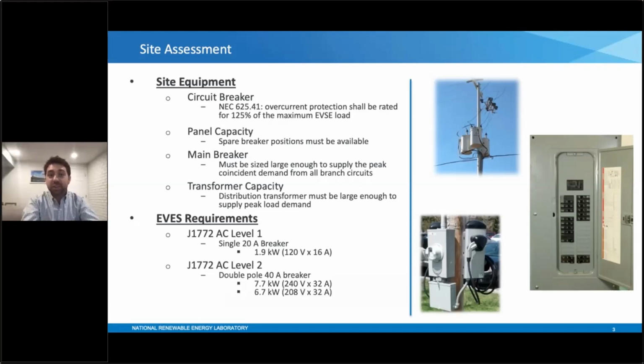Then you also need to look at panel capacity, specifically the spare breaker positions available. Looking at the picture on the right, each of those rectangles available below the previously installed circuit breakers is referred to as a breaker position. The number of breaker positions available is really important in terms of planning how many EVSE you can install with your current infrastructure.